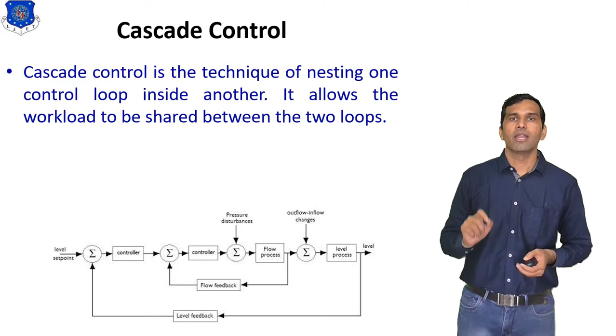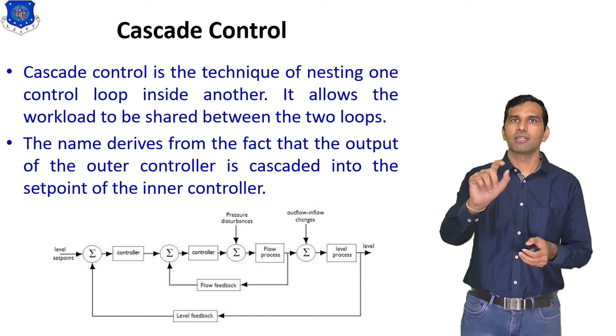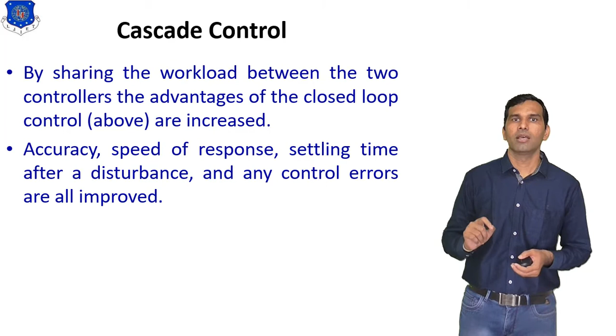The name is derived from the fact that the output of the outer controller is cascaded into the set point of the inner controller. Here we can see this is the outer controller, and its output is cascaded into the set point of the inner controller. So that's why it is given the name cascade controller. By sharing the workload between two controllers, the advantages of closed loop control are increased. This is one advantage of cascade control over the feedback control system. The accuracy, speed of response, settling time after a disturbance, and any control error are all improved in this control system.